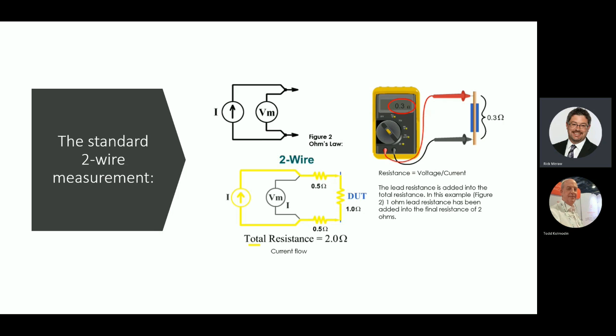This happens in all electrical measurements. I know that some manufacturers have different ways of dealing with it. We do a calibration, and for example, on our machines, we do a calibration down to the probe tip itself, and then we save these values, and these values are accounted for in every resistance measurement that is in the lower range.